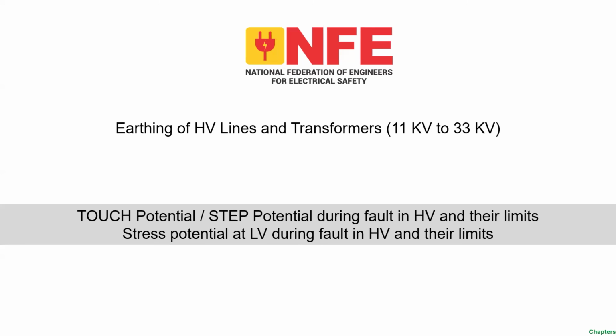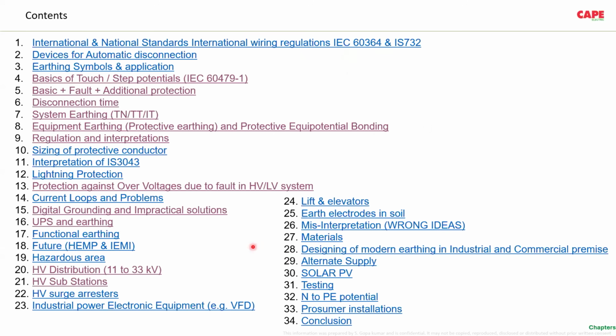Today we are going to discuss the touch potential and step potential during a fault in the high voltage system and their limits, meaning the limits of touch and step voltage, which have to be below the tolerable limit in order to avoid shock to human beings. Also the stress potential of low voltage during a fault in high voltage and their limits. I will also try to explain a little about what measures we can take to get safety from these or to keep the potentials within the limit.